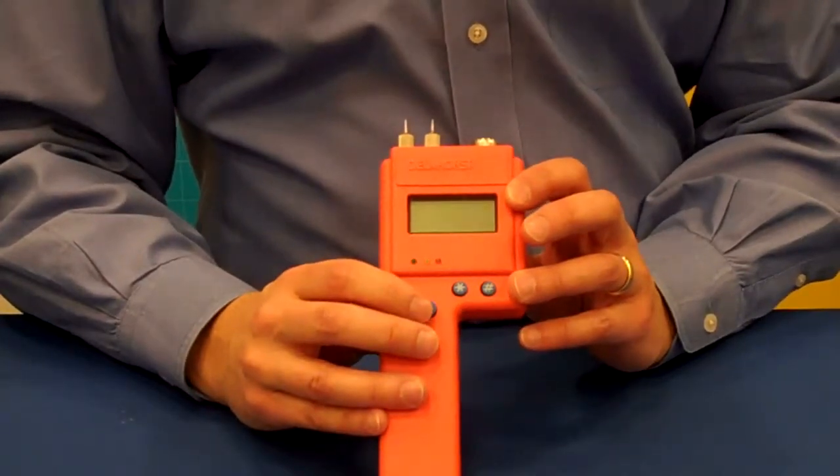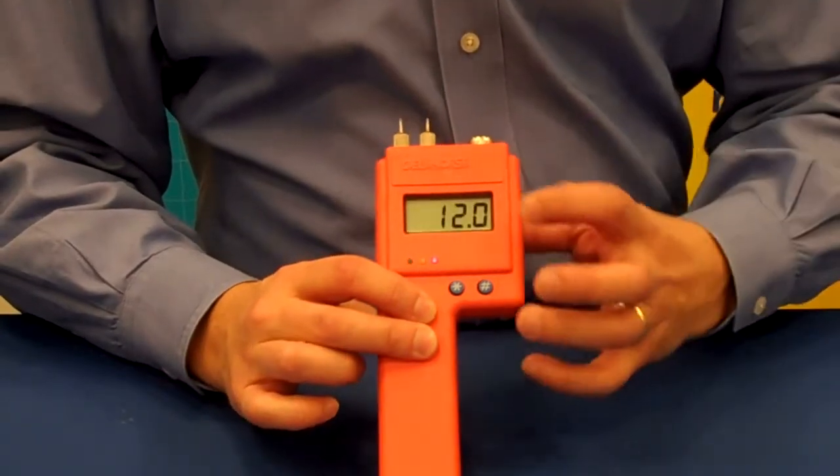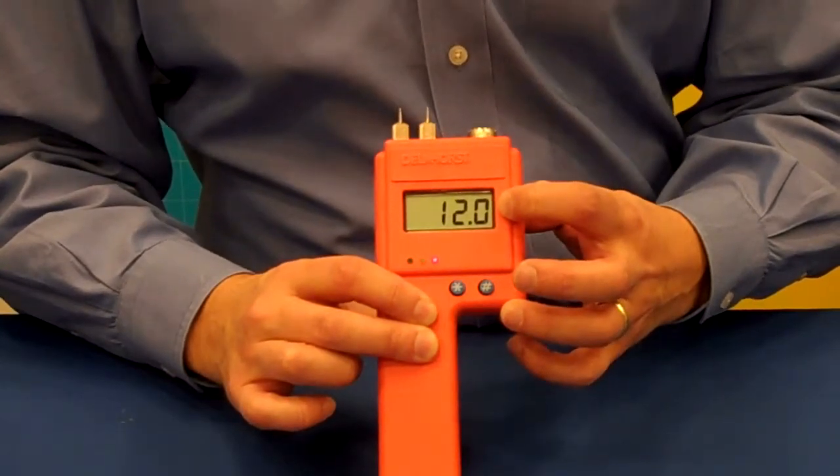A couple of other features in the BD2100 are the built-in calibration check. By pressing these two buttons together, the meter will read twelve percent, which just tells you that it's electrically in calibration.